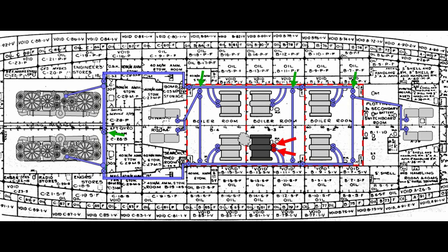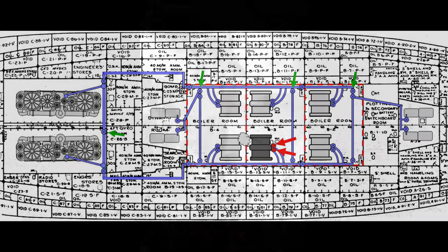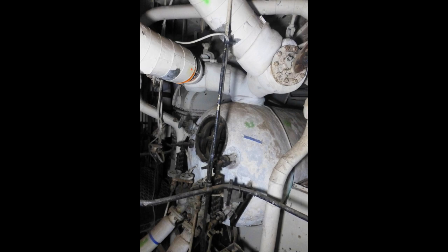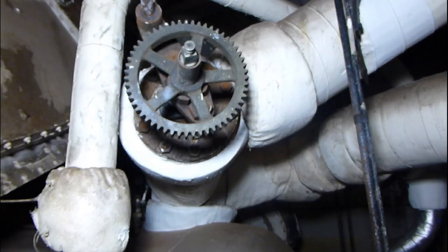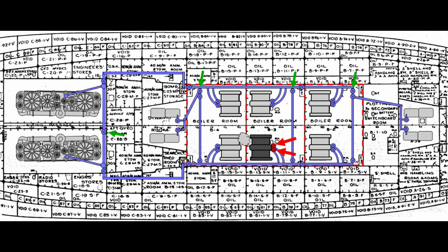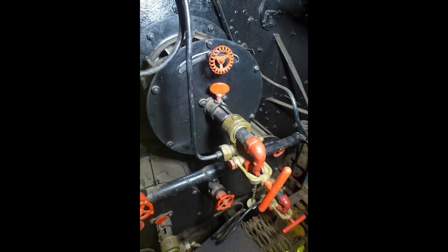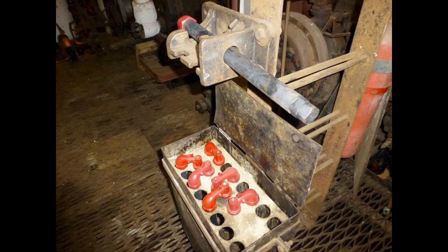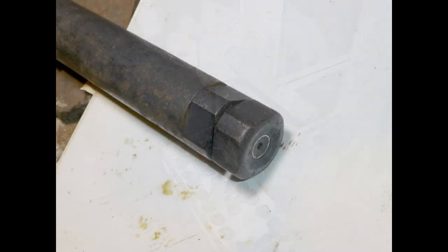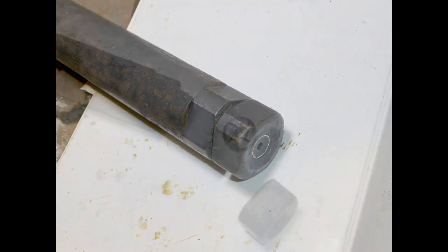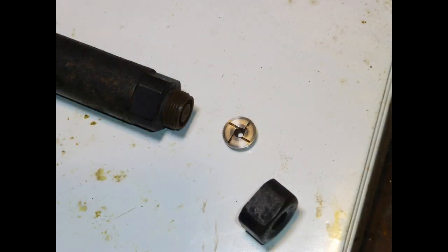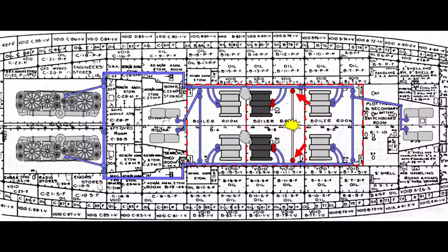Say there's a tube failure or firebrick collapse resulting in the loss of a boiler. Three stop valves and the cross-connect valve are immediately closed to isolate the boiler from the system. Also notice that other cross-connects have been opened to reunify the system and provide balanced steam to both engines. Loss of the boiler is made up by changing to larger burner tips and boosting forced draft air to increase boiler output. However, overfiring them can damage boilers, so it's only a temporary solution.